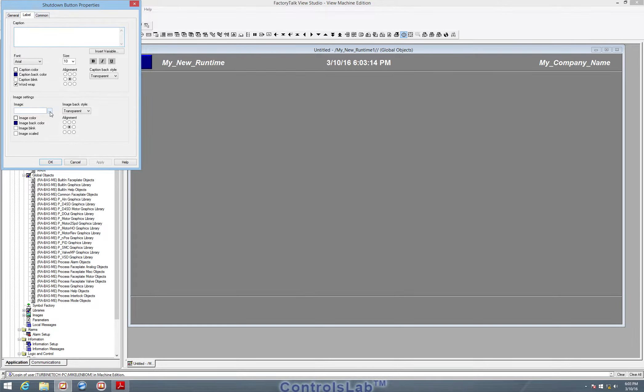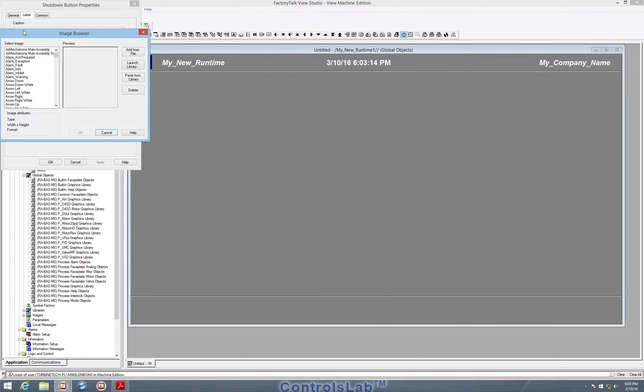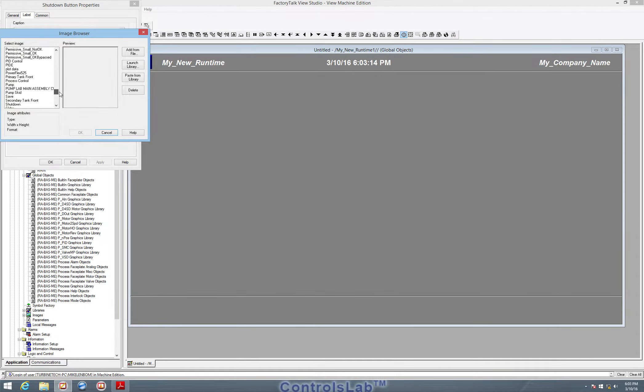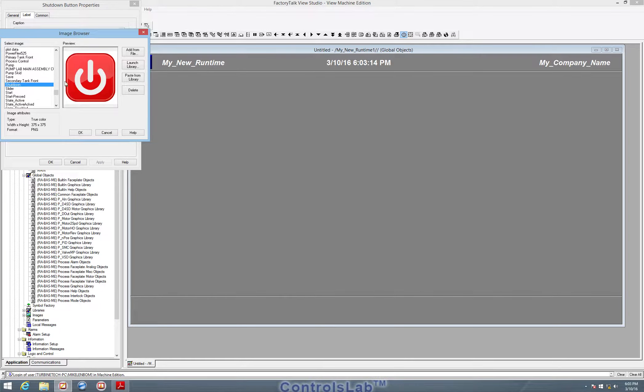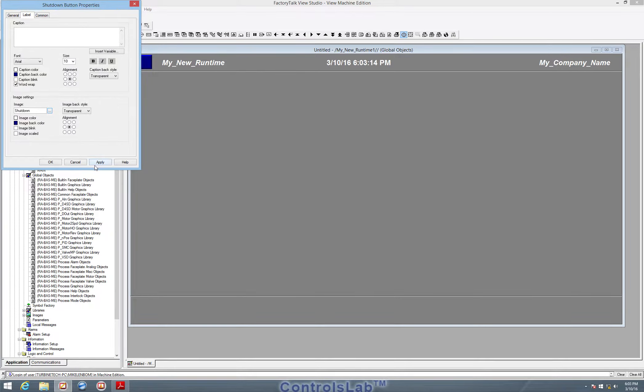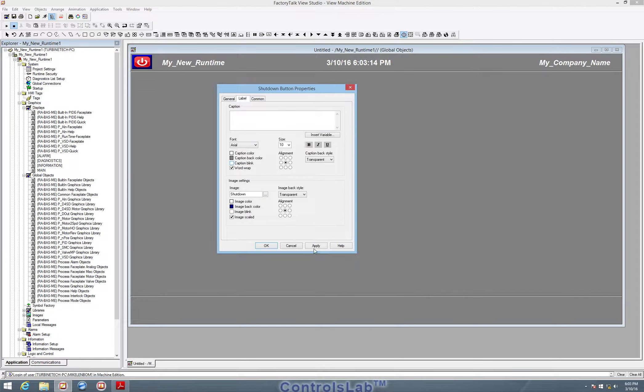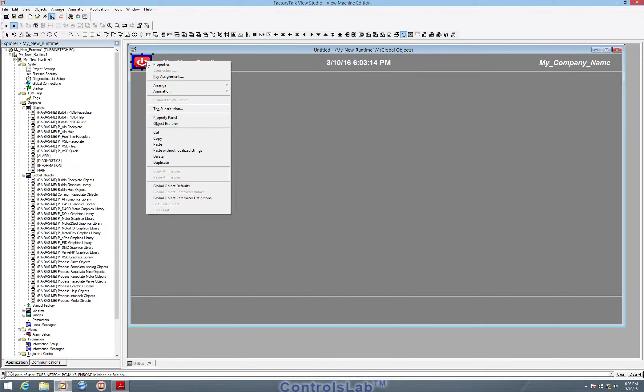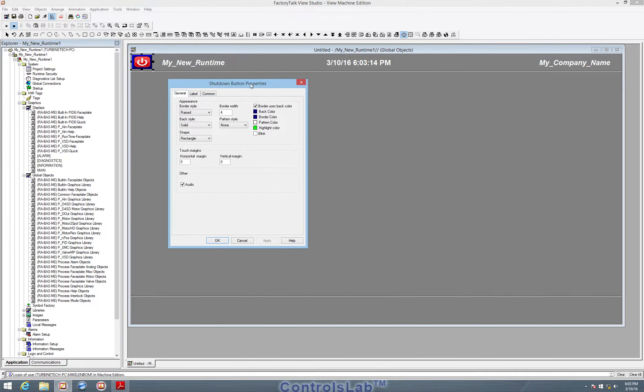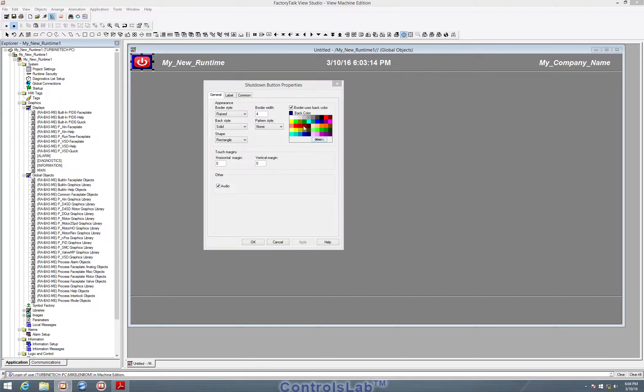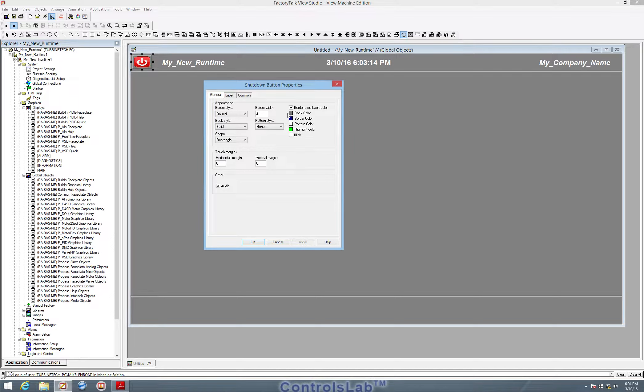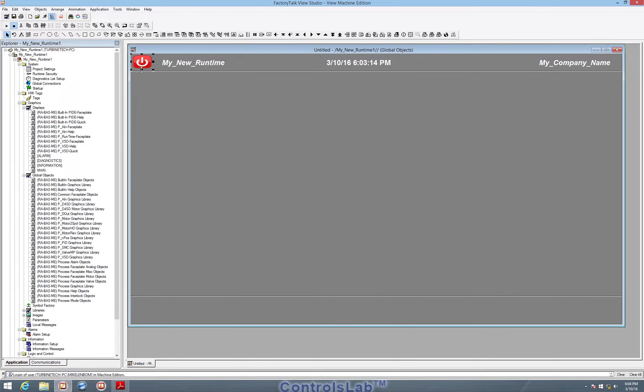And we are going to actually go select an image under the label category for that button. We're going to go into our library because we already have a shutdown button in our graphics library. So we can add that button, hit apply, and we also have to do image scaled. Hit apply. That will scale that button to the area that we had picked. We see our blue back color that's bleeding through that button. We're just going to select gray. And I think that's the back color we need to change. And then we'll get rid of that raised panel. And hit OK. So now we have a nice power button to shut down the HMI when it's running.